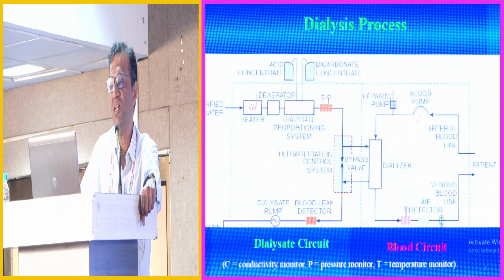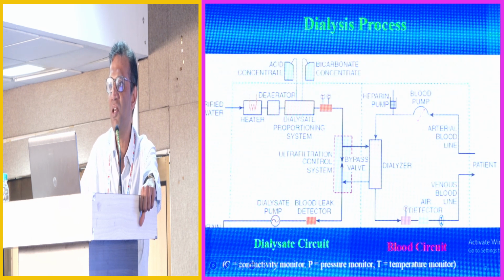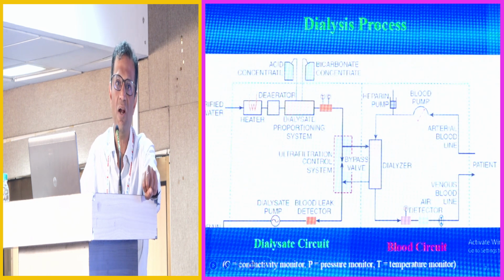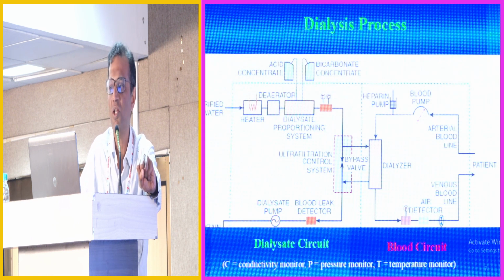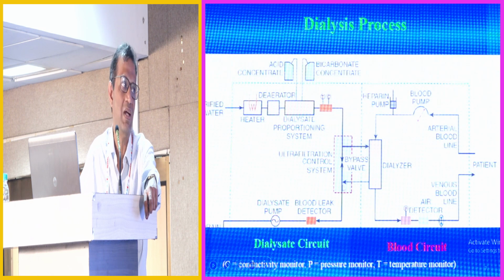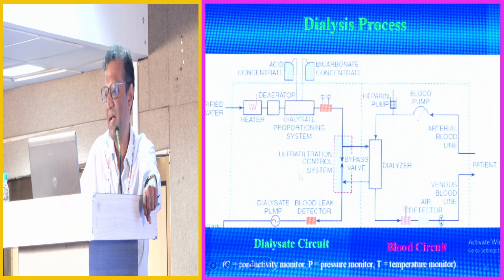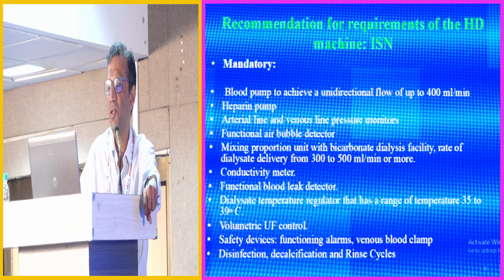We can think of the dialyzer as something of an interface. So you have a blood circuit here on the right hand side, which consists of bringing the blood from the patient with a blood pump and returning it to the patient without producing coagulation or hemolysis along the way. And within the machine, you have the preparation of the dialysate, which is also delivered to the dialyzer and then taken back by the machine to drain.